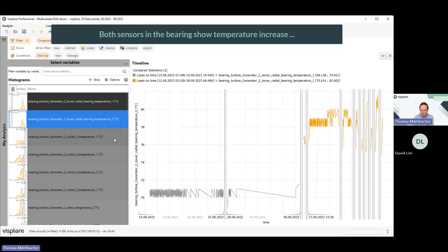And this was an interesting insight for them, that actually Visplore showed them the only sensors that have changed are the bearing temperatures themselves. So they said, okay, it's not ambient conditions causing this. It's not parts like the coolers causing this. The problem has to be in the bearing itself, because only the bearing heats up. And this gave them the confidence to tell the field operators, please open up that bearing and look for physical damage. And this is what they did.